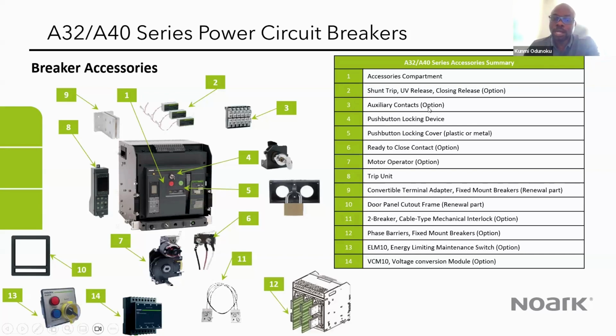You give a close command to the breaker. We have the auxiliary contact, and the push button locking device, which is in front of the breaker. We also have the cover, which is available in both plastic and metal. We have the ready to close contact option, which is an indication that the breaker has been charged, whether manually or through the motor operator, and is ready to close.